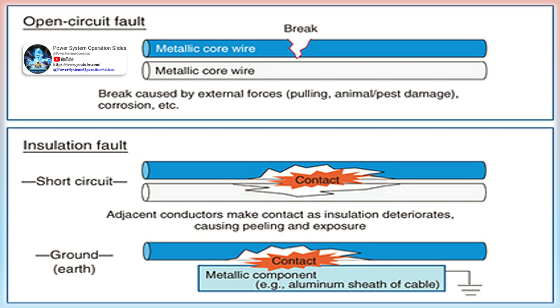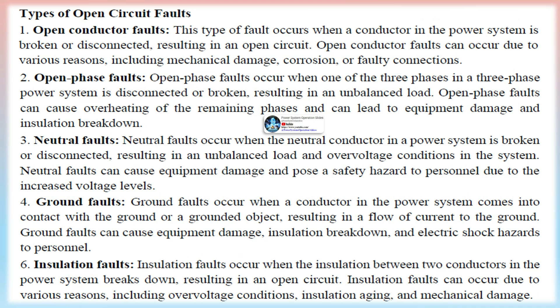Various techniques are used to detect open-circuit faults in power systems. Regular visual inspections can help identify potential faults including broken or loose conductors, damaged insulation, or faulty connections. Voltage and current measurements can detect open-circuit faults, as levels change when a fault occurs — for example, an open-phase fault can result in a lower voltage level in one of the phases. Impedance measurements can also detect open-circuit faults, as a fault results in increased impedance, measurable using time-domain reflectometry or frequency-domain techniques. Power quality monitoring can detect faults through changes in parameters such as power factor and harmonics.